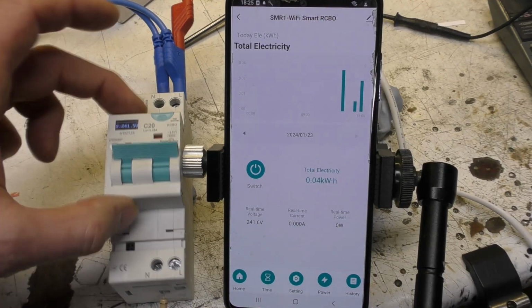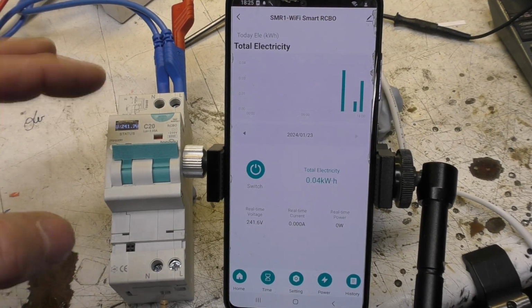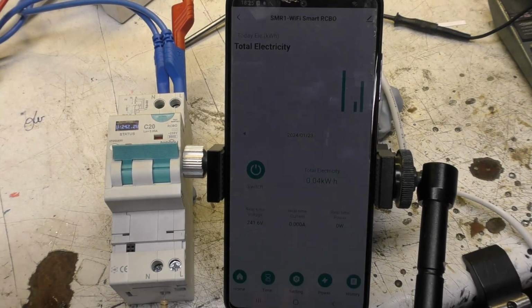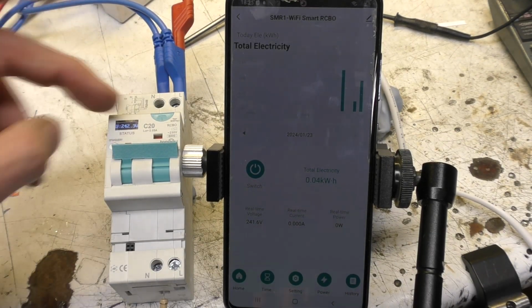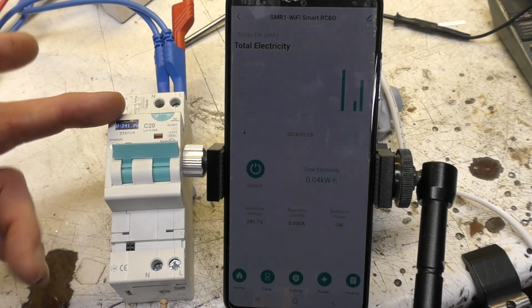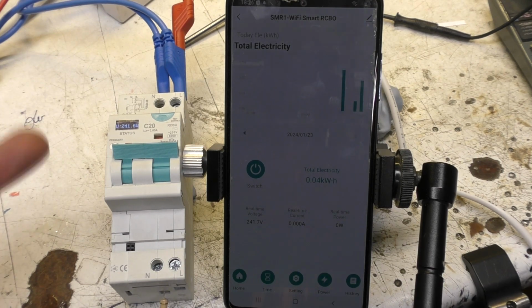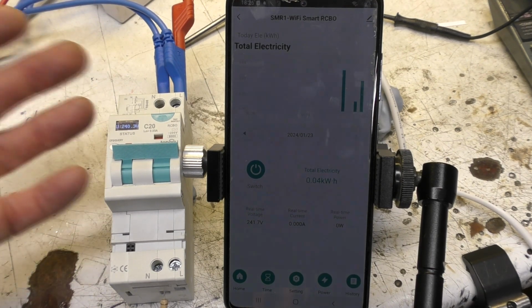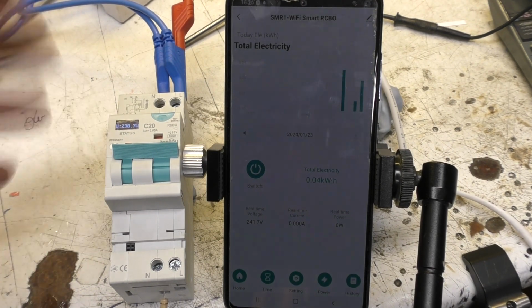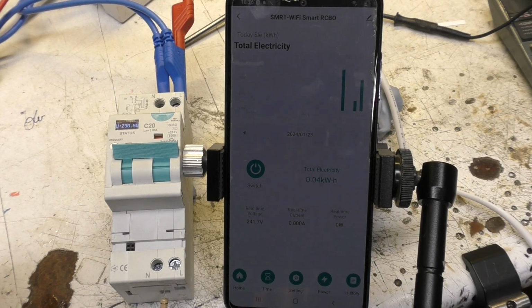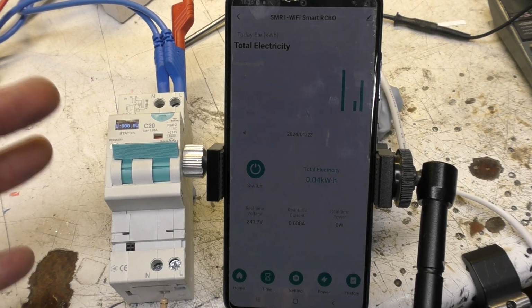But if your local distribution box has one of these in it, that gives you a lot of very useful information for quickly debugging and fault finding. You've got the voltage, current, all this information there, including earth leakage. So let's say you're getting occasional RCD trips, and you see that the normal leakage is hovering around 20-30 milliamps. Then that gives you information as to why that's happening.